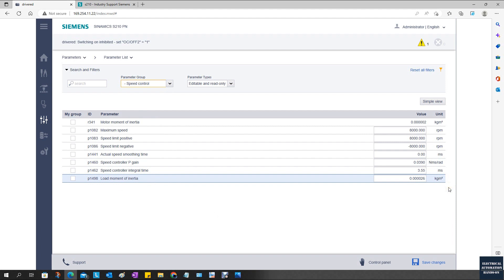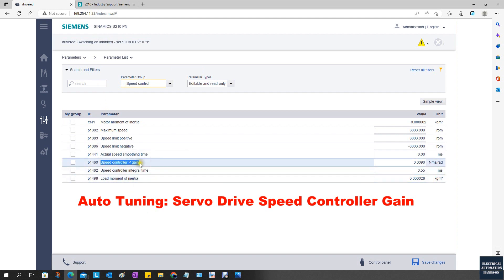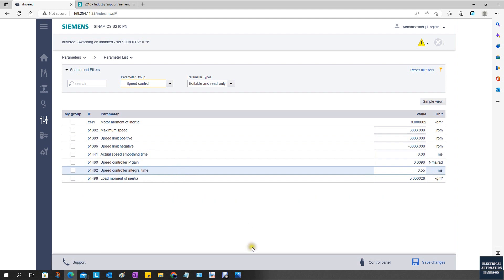While the servo motor is doing positioning control, the positioning gain will be set from the controller. The positioning gain will be transferred via the control word. You do not need to worry about this P-gain parameter. After the auto-tuning, that is the speed controller P-gain and the integral.